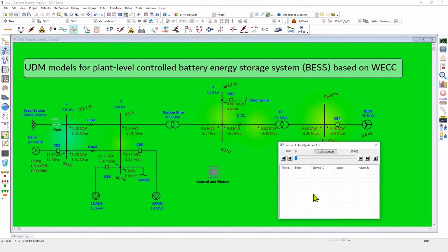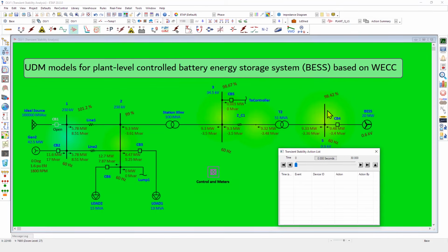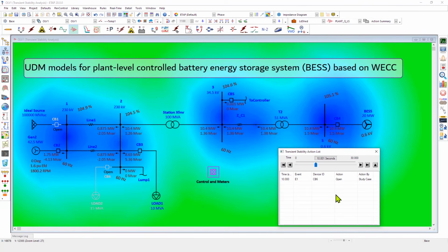So let's set our simulation back to time equals 0 and observe our one-line diagram. We can see that the yellowish color corresponds to slight under voltage in the system, whereas the blue color corresponds to slight over voltage in the network around our nominal value of 100%. We can then move our action slider to the next action in our sequence, where we're defining circuit breaker 6 is open at time equals 10 seconds.